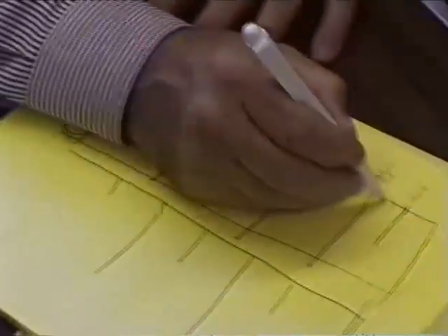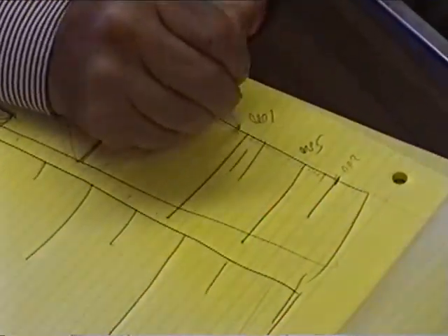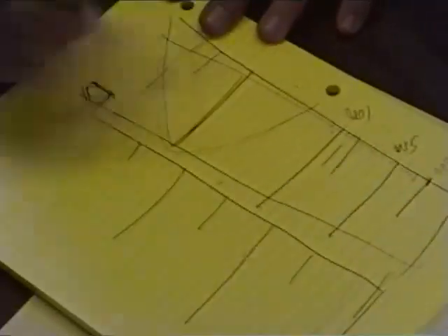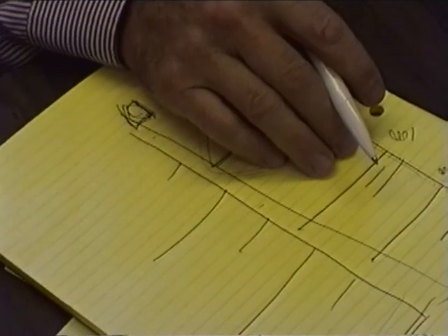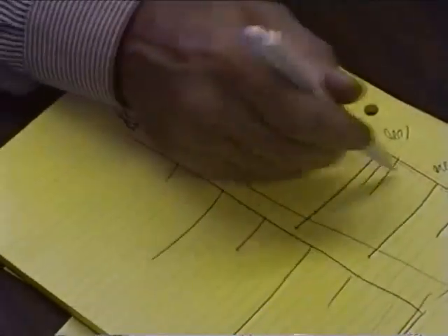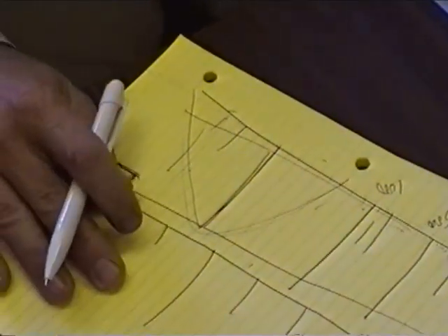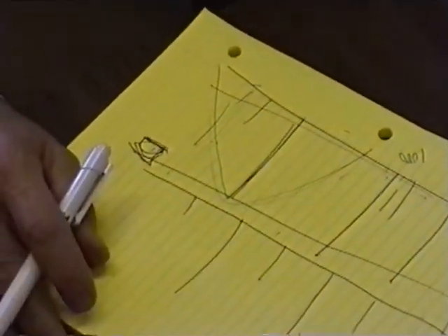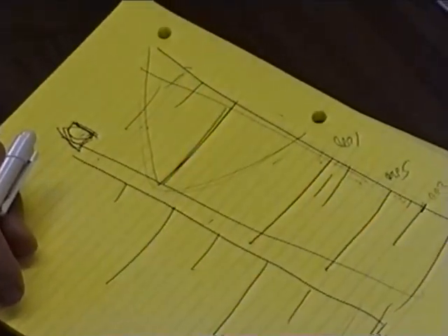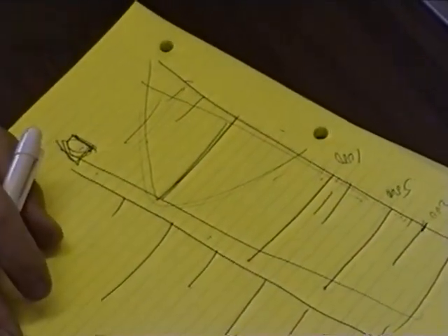You only pick it up sometimes where you see the background appears bigger in one than the other, unless you know to look. And this is where that problem can come up, where you've acquired a whole bunch of runs. Hey, they look pretty good at this level, but that's because it's normalizing everything. If you back up, you find that one, it missed everything. Run didn't even run. It's 1/10 or 1/20th the amount of material, which is what we get carryover between runs.